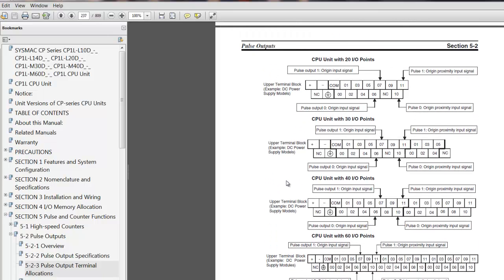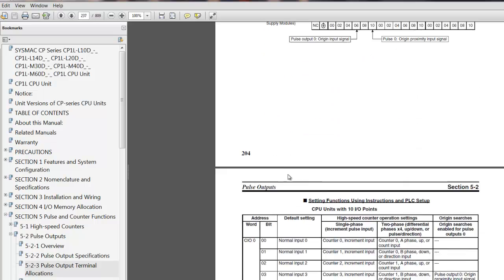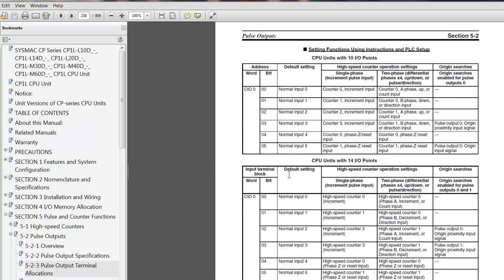So a key point here is that as you're buying the I/O system, if you're buying a 20 point PLC and you're wanting to do two axes of motion control, you're probably going to be using four points of output and probably two to six inputs depending on what kind of limits you might have on actuators. So that will take away from usable I/O, and it's as you might expect, but just a good key point nonetheless.